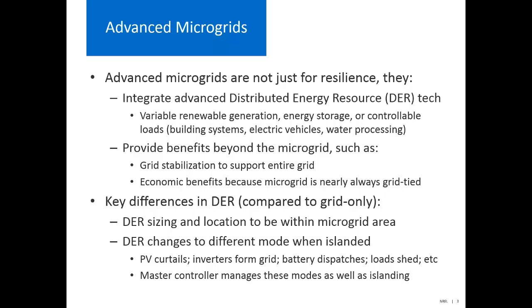Advanced microgrids, unlike traditional ones, don't just care about their downstream loads. They also care about upstream features, such as providing grid stabilization to support the entire grid during a disturbance, and providing economic benefits to help pay for these expensive pieces of equipment while they're grid connected, because they nearly always are—over 90% of the time. We're trying to use the microgrid controllers and the microgrid itself to generate revenue to help pay for the equipment, while also keeping it available for when we have a grid contingency and need to go into islanded mode.